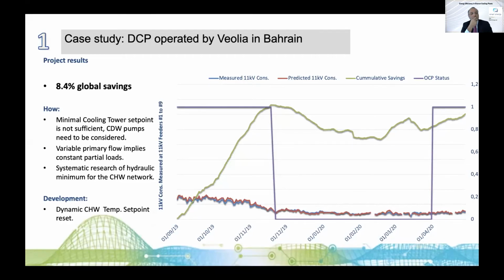I mean, this is a variable primary plant. There are quite high limitations on how low the primary flow can reduce, and having a chilled water temperature set point reset is an improvement that we're testing right now.